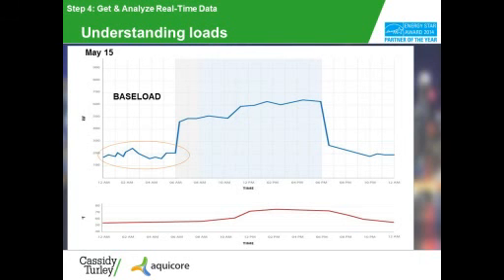And then you can see that the base load went back to normal, and right around 6 a.m. the building started back up. And if you look down below on the red line, it shows the temperature. It was a nice low 50s degree morning. So that next tier is where the building operated on economizer. I'll highlight that for you in just a minute. There you go. So there's where the building started. It was 52 degrees outside, nice cool morning.